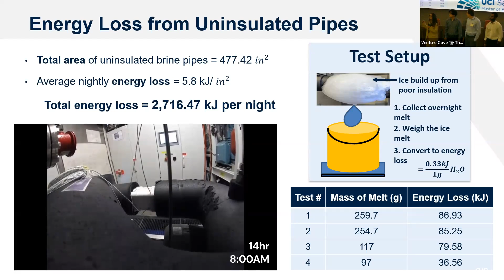In order to characterize this, we averaged 4 nights of ice melt. We used the latent heat of fusion and calculated the mass melt per square inch per night. Using the total uninsulated surface area of these pipes, we found the average nightly energy loss to be 2,700 kilojoules, which is a pretty low number, meaning the insulation is not really impacting the station too much.